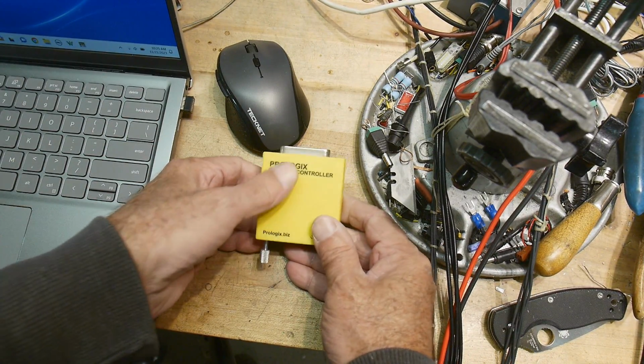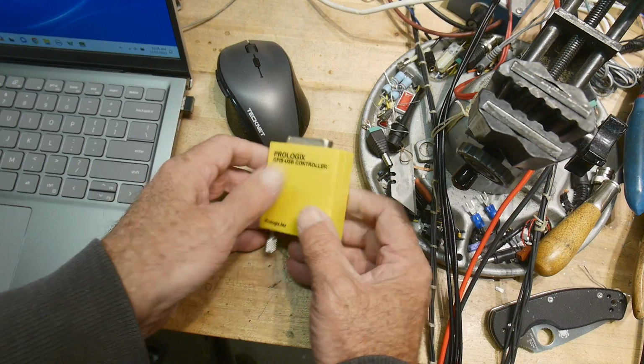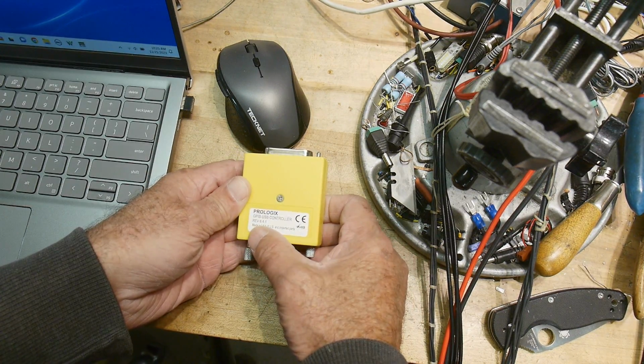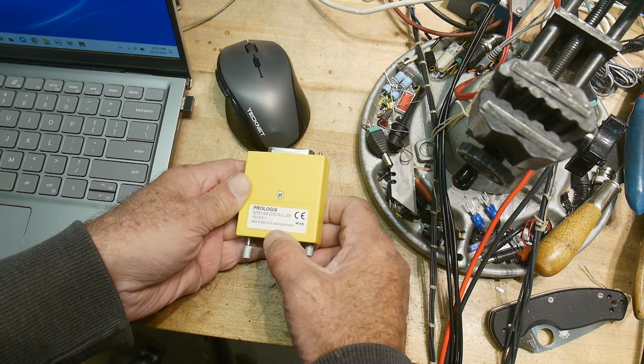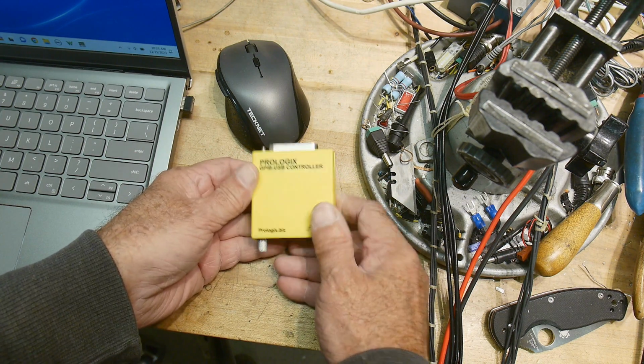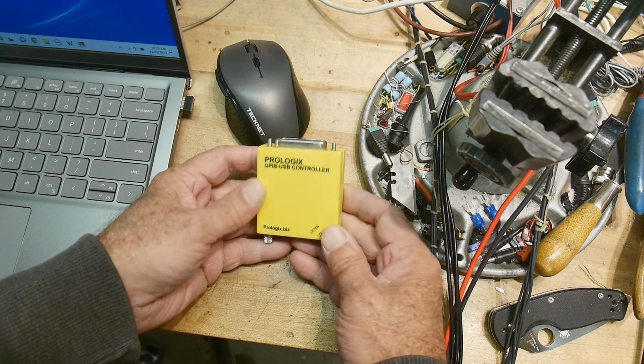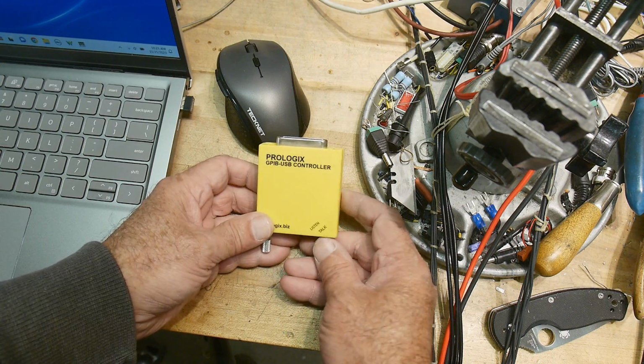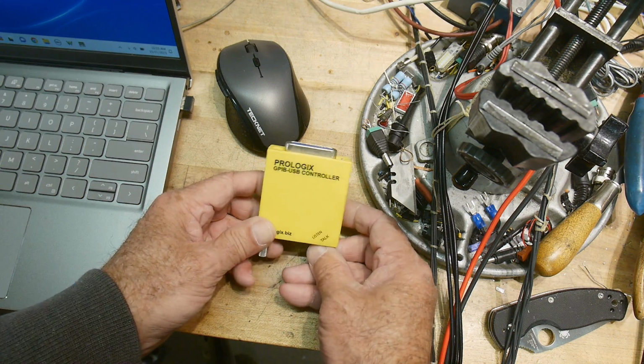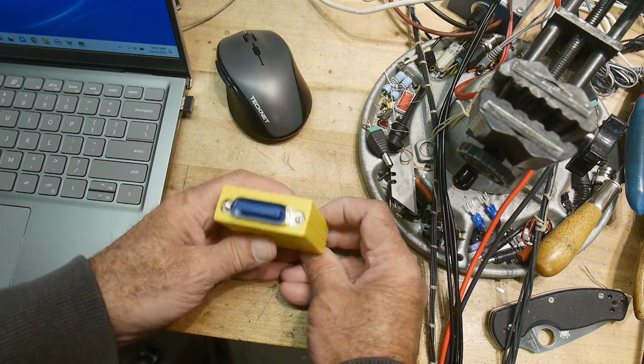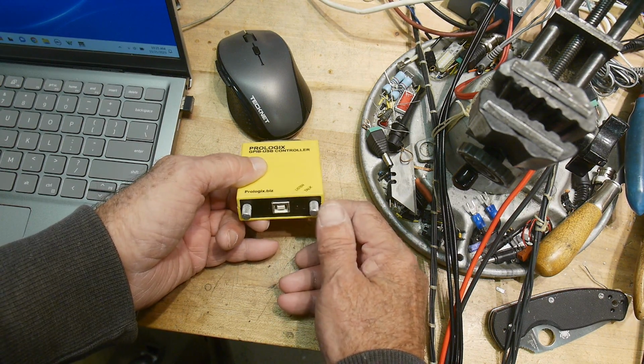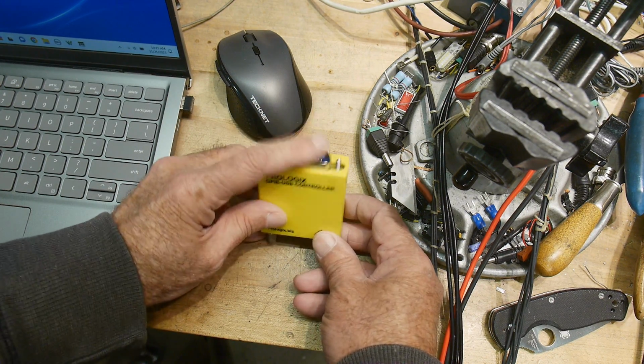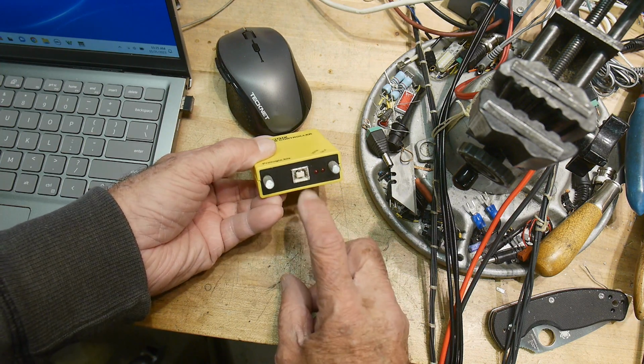All right, so you need to have some type of interface box. I happen to have a Prologix. This is revision 6.4.1. Anyway, these are about, I don't know, 150 bucks, 200 bucks. I actually asked my wife to buy this for Christmas a couple decades ago because they were expensive. It converts IEEE 488 to USB.